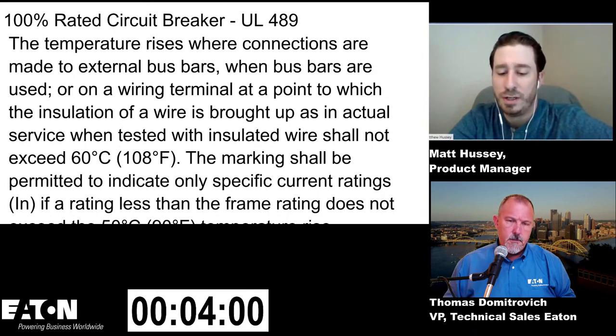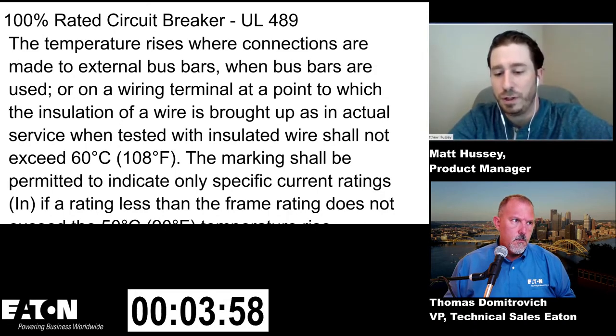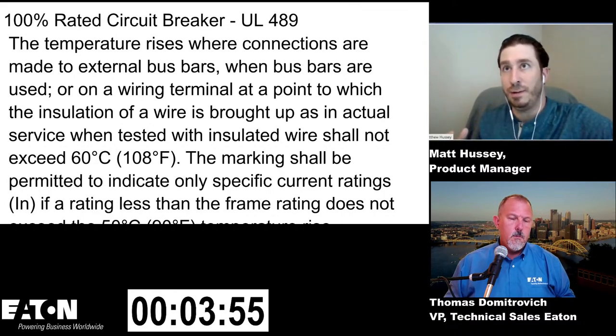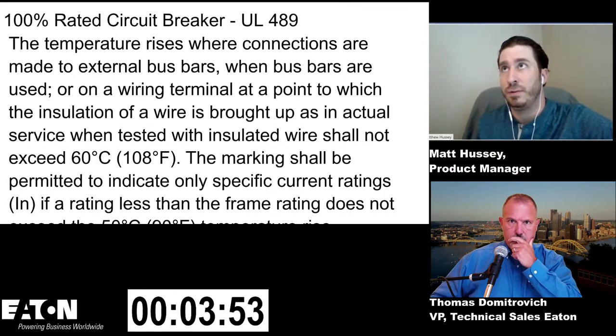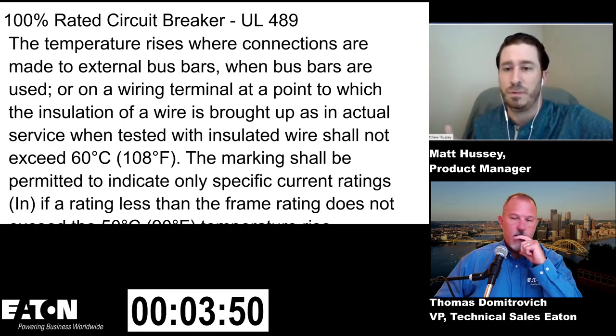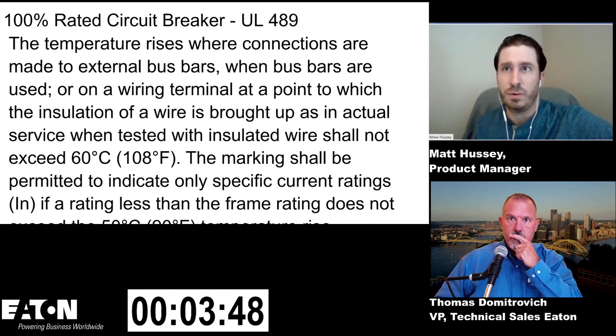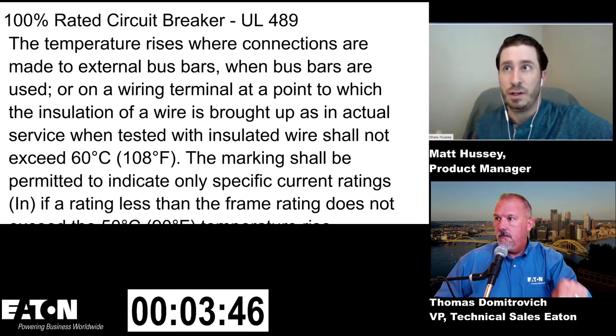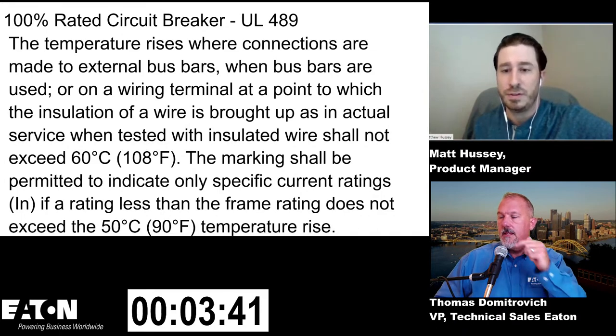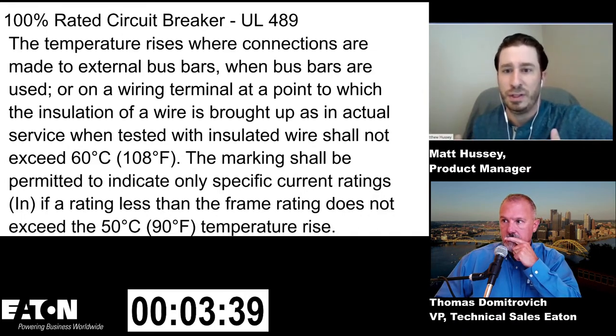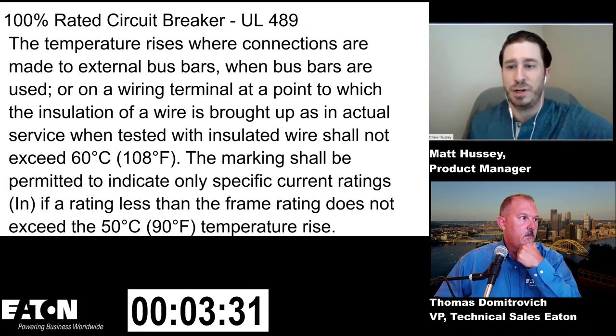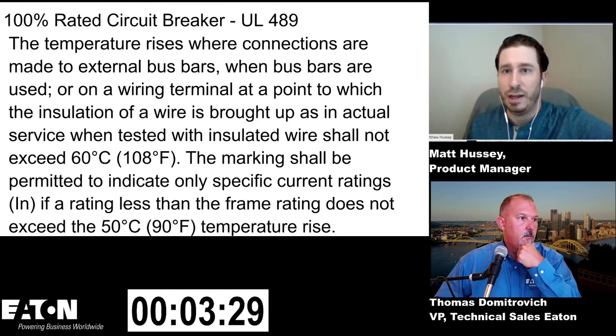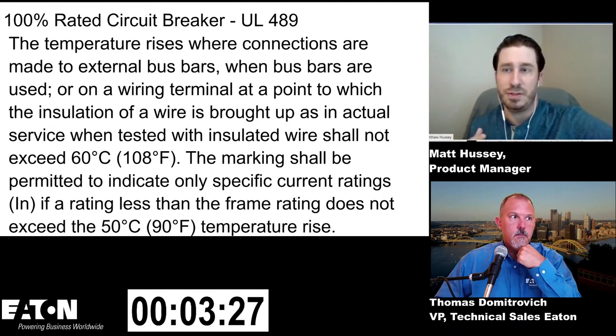Yeah, usually temperature rise is focused around not exceeding a threshold above ambient so that either one, the device fails to perform its intended function, or two, it gets so hot that you start damaging other components, or chiefly conductor insulation.